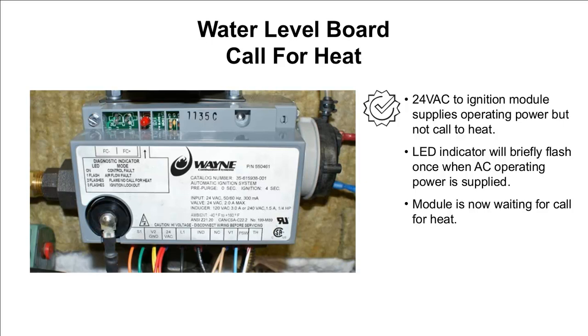Finally, the red wire terminates at our ignition module. It is only supplying 24-volt operational power to the module. The LED indicator on the module, which is located right here, will flash briefly when that AC power is supplied. So this is another good visual ID. Fill the unit with water, power it on. There is a brief flash on the ignition module that also tells you, hey, my AC circuit is satisfied. But I will say it is a quick flash, so you should be watching for it.